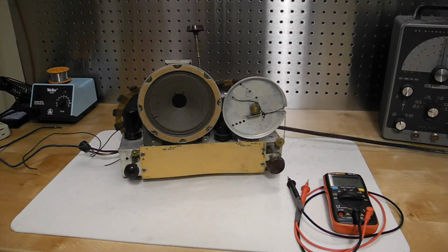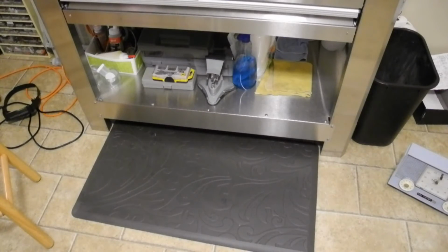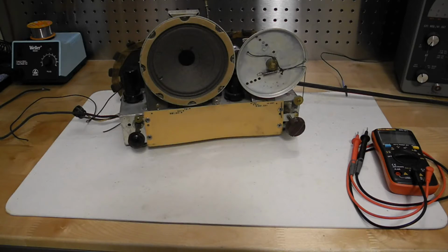Your work area should be made of a non-conducting material such as wood. Ensure you have adequate space for the equipment under test, test instruments, and any tools. Working in bare feet on a damp concrete floor is a recipe for disaster. Wear insulated rubber shoes such as running shoes, or ideally work on a rubber mat, which is also good for reducing fatigue from standing. While not an issue with vacuum tubes, solid-state equipment can be sensitive and damaged by high voltages caused by static electricity. Use a static safe work area with an anti-static mat and/or a grounded wrist strap.